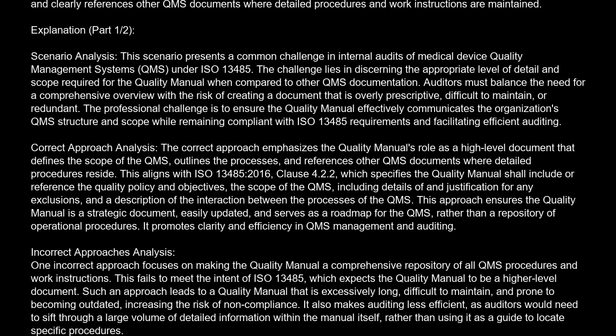Correct approach analysis. The correct approach emphasizes the quality manual's role as a high-level document that defines the scope of the QMS, outlines the processes, and references other QMS documents where detailed procedures reside. This aligns with ISO 13485 2016, Clause 4.2.2, which specifies the quality manual shall include or reference the quality policy and objectives, the scope of the QMS, including details of and justification for any exclusions, and a description of the interaction between the processes of the QMS. This approach ensures the quality manual is a strategic document, easily updated, and serves as a roadmap for the QMS rather than a repository of operational procedures. It promotes clarity and efficiency in QMS management and auditing.